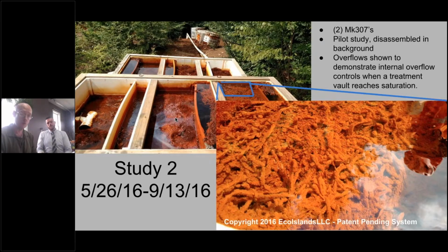But with the true MRUs, we were able to run this thing up to around 70, 80 gallons a minute at some of our best rates, or some of our highest flow rates. And as it turns out, right around 60, 65, 70 gallons per minute is actually the flow rate you want to run one of these systems at, because dissolved oxygen is one of the primary limiting factors within this system.